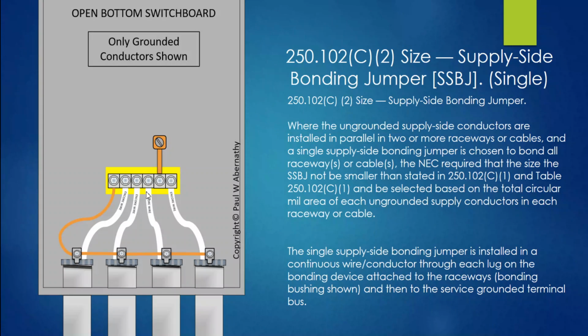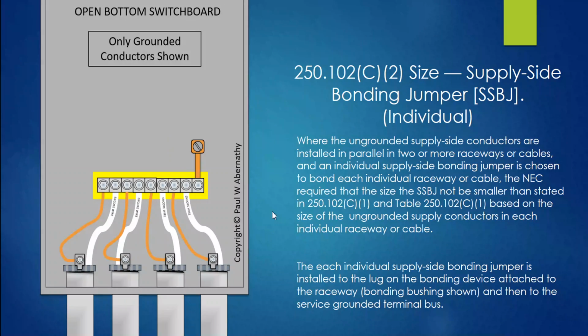Well, that's pretty simple. I'm going to go and put a 250 kcmil through here. Now, again, if these lugs can't handle it, or they go up to a certain size, depending on the type of bonding bushing you have, then you might have to go to another option. And here's your other option. So in this option here, I am simply running a single in parallel to each one of these raceways. And I only have to use the conductors that are within this raceway. So I take the largest, in this case, ungrounded supply side conductor here, and I use that in order to size my supply side bonding jumper. So this was a 500 kcmil.